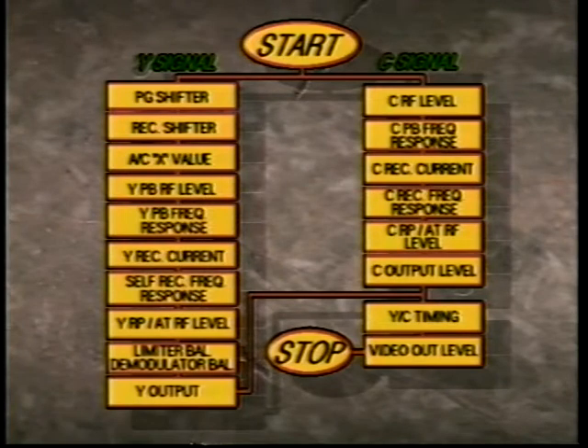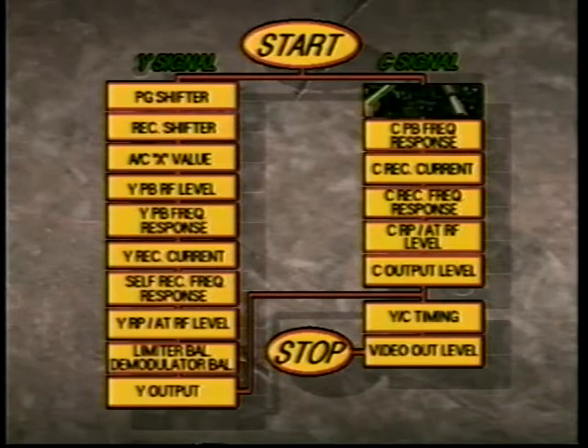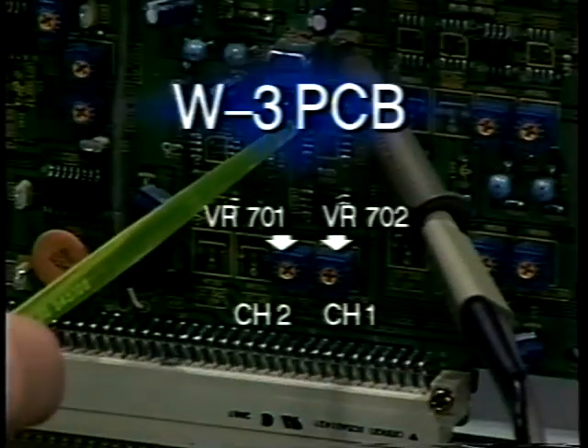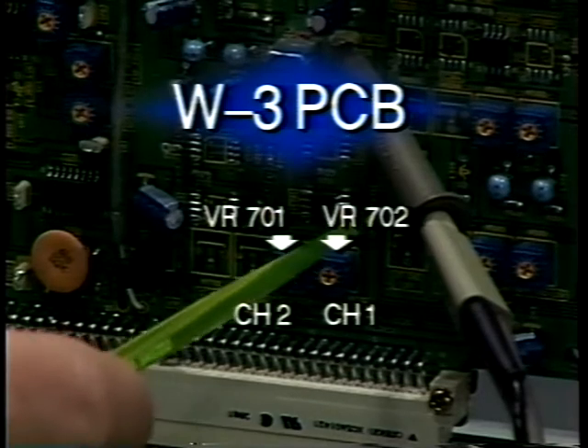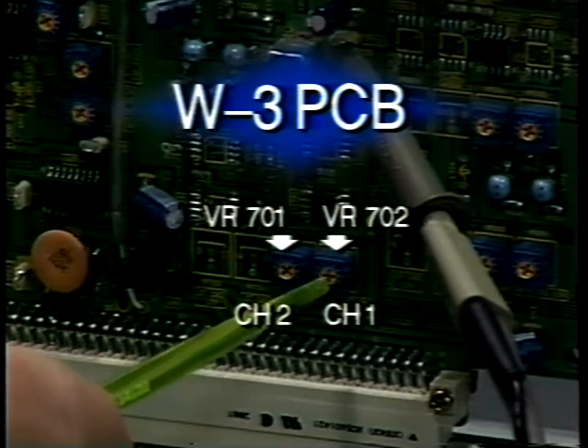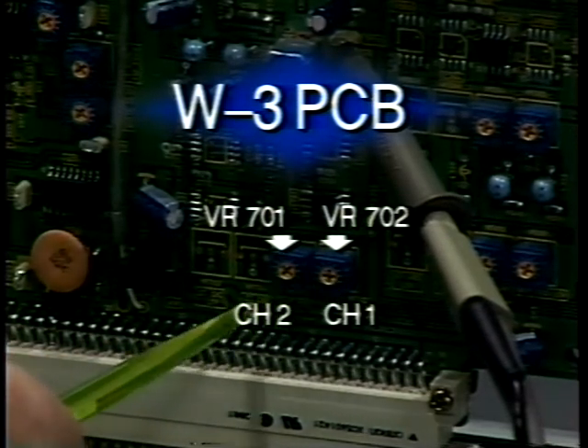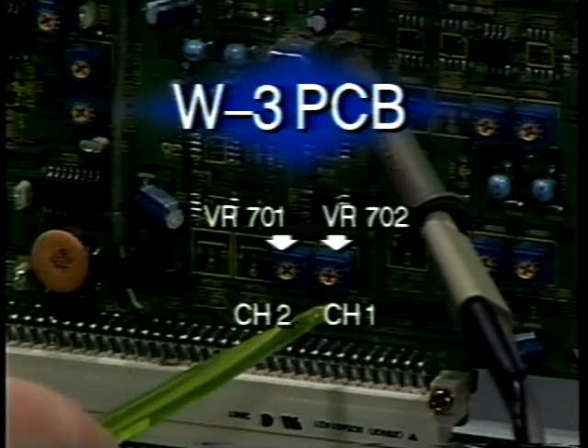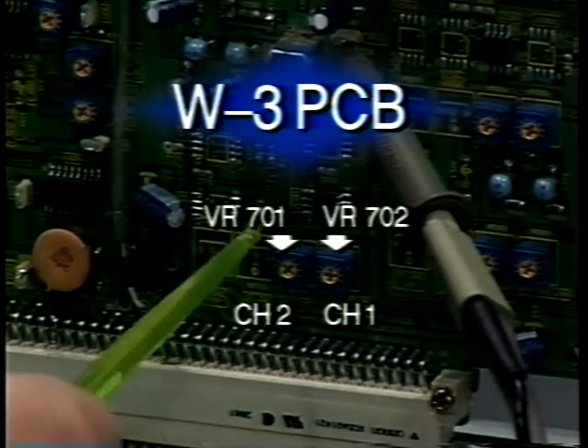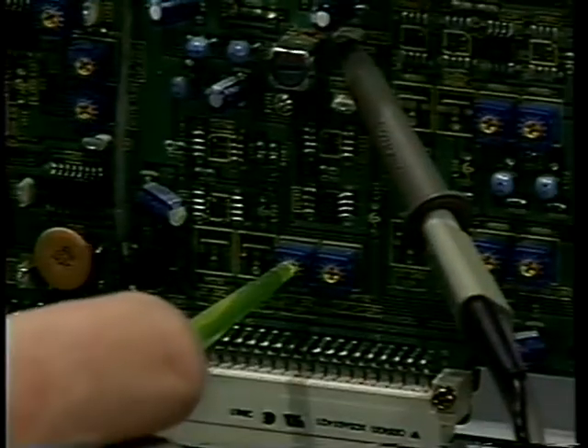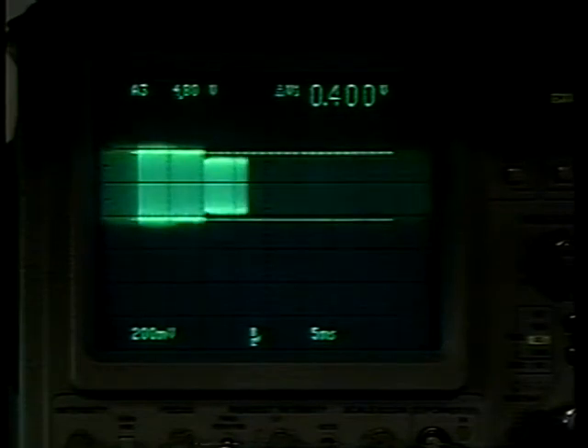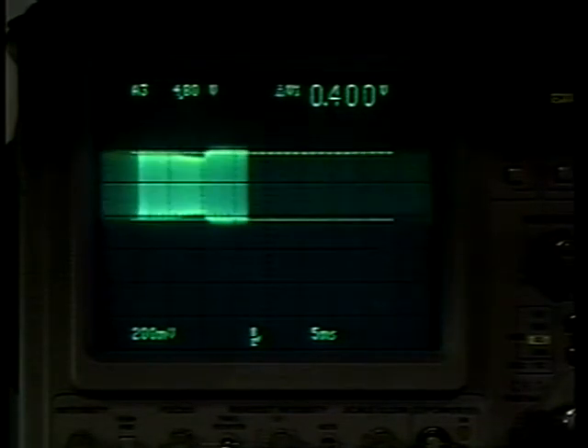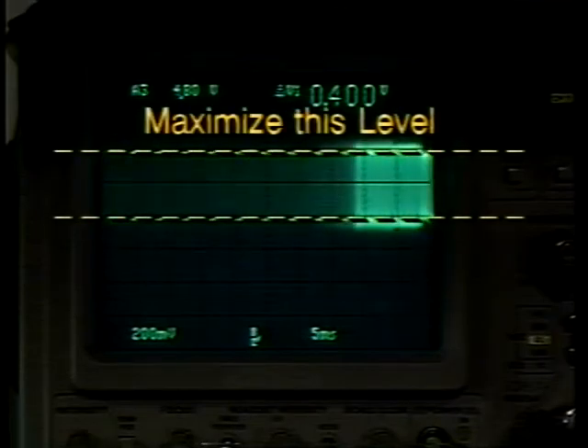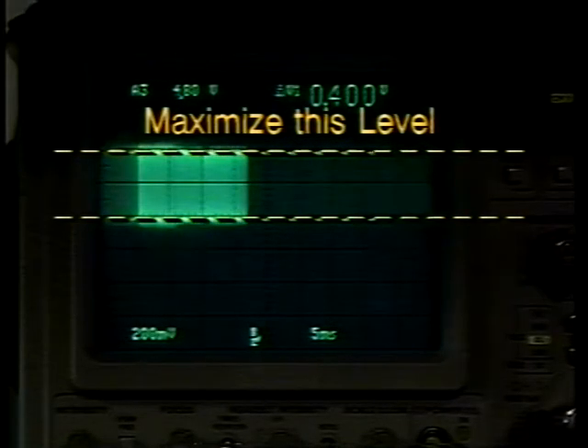This is step 1 in adjustment for the C signal side in the simplified head replacement flowchart, the CRF level adjustment. We're going to use TP701 on the W3 board and the adjustment pots VR701 and 702. 701 is for channel 2 and 702 is for channel 1. Our first adjustment is for channel 2. Observe the waveform monitor. Now adjust channel 1 and observe the waveform monitor again. This is a properly adjusted waveform.